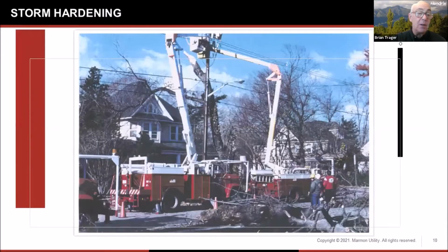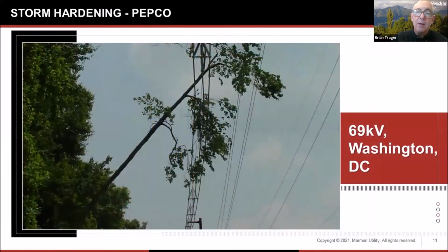Somebody drives by at some point and calls the utility, says, hey, there's something wrong here. They come, they cut the tree down, they lift that bundle back up with the equipment handler, put it on a new bracket, and they're done. They've never had an outage. So this is everything to do with reliability, quality of service, minimizing safety and SAIDI. And we've got dozens, hundreds of these photos.